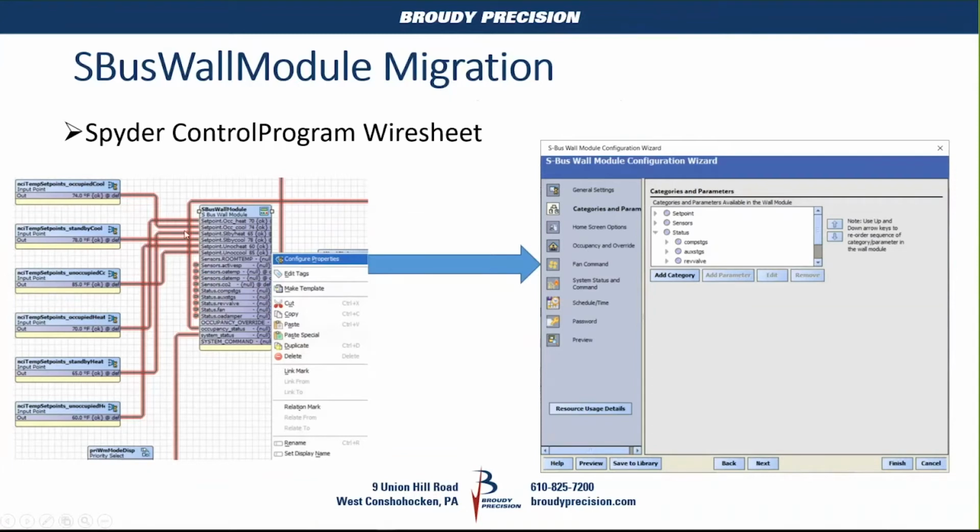This actual link is two ways. So when you change the value on this point, it changes it on the ZIO. If you change it on the ZIO, it actually comes back and changes it in your NCI in this point here. In the CIPer 30, it doesn't work that way.